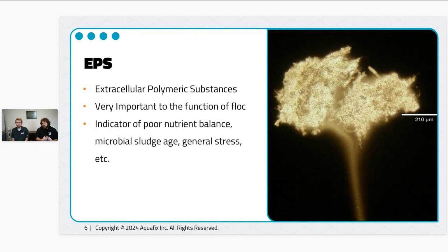So I would say that in an MBR application, you're working against the nature of the system itself that's trending towards larger floc. But if you can keep those floc in that upper end of moderate size, so probably 300 to 400 micrometers, you'd probably see good success. It's just not really tenable to do that. It's not very actionable advice for an MBR.